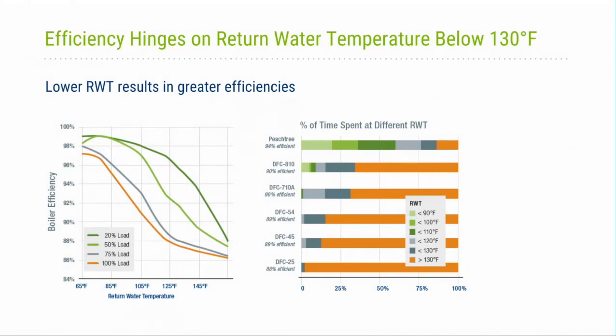The different lines on the graph are the percent loading. And so this is a little counterintuitive for some of us engineers, but you actually get higher efficiency with condensing boilers at lower loads. As you get down to low loading, they really perform well. And so what the graphic on the right shows is the percent time spent at different return water temperatures for the 5 different buildings we looked at, the Federal Center and then the Peachtree.